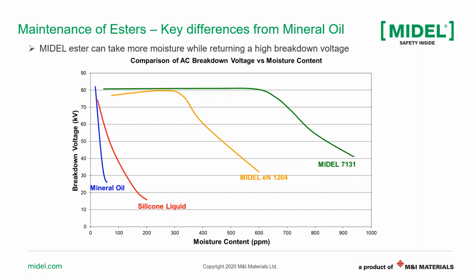Now we can look at the breakdown voltage, because it is one of the basic parameters we check to assess our transformer. On the chart in front of you, the x-axis is the moisture content in ppm, and the y-axis is the breakdown voltage. You can see four liquids here: the mineral oil, the silicone liquid, MIDEL EN1204, which is a natural ester, and MIDEL 7131, which is a synthetic ester.